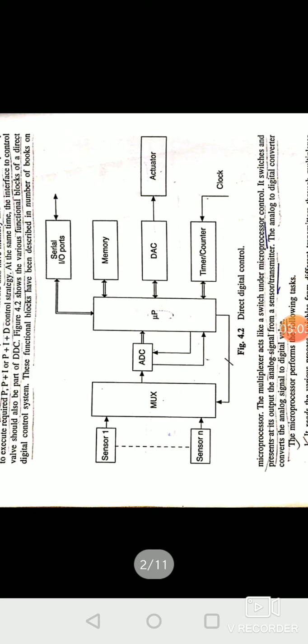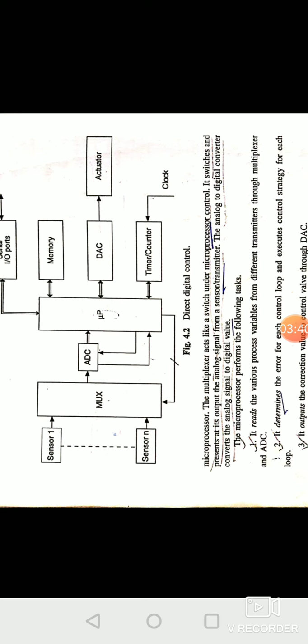And here we have some functions that can be performed by a microprocessor. First, it reads the various process variables from different transmitters through the multiplexer and analog to digital converter. It determines the error for each control loop and executes the control strategy for each loop. Then it outputs the correction value to the control valve through the digital to analog converter. And then we have memory, a timer counter circuit, and a serial input output port for connection to a physical network. Now we will do DDC software.